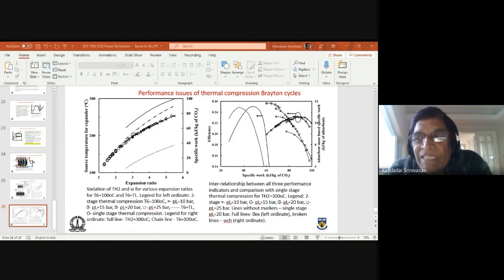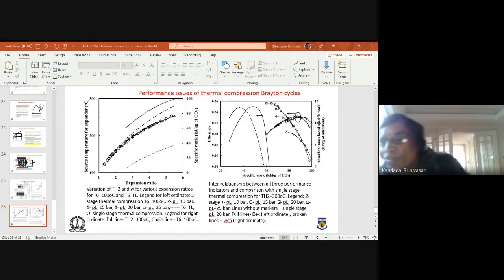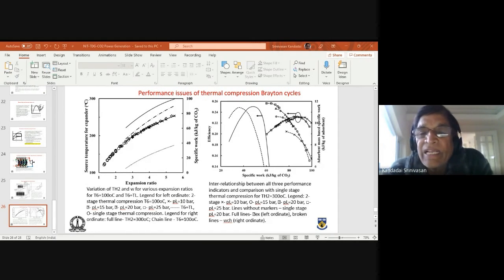In some cases, they do recover that heat because the exhaust is still at about 180 to 200 degrees, quite warm. So what you can do is apply what is called a bottoming cycle - an organic Rankine cycle, where an organic fluid like acetone or 134A is used, and that heat is used in the boiler of those organic Rankine cycles. So you still produce some power. Whatever you produce, you just use it. It may be very small - maybe in a 100 megawatt plant that may produce only about 1 megawatt, but still 1 megawatt is not bad.